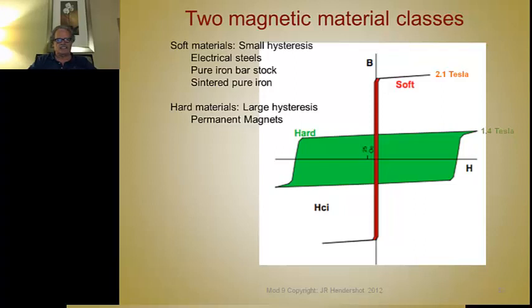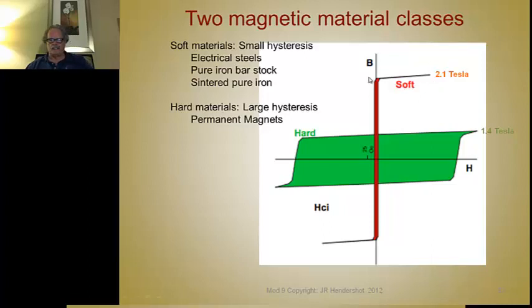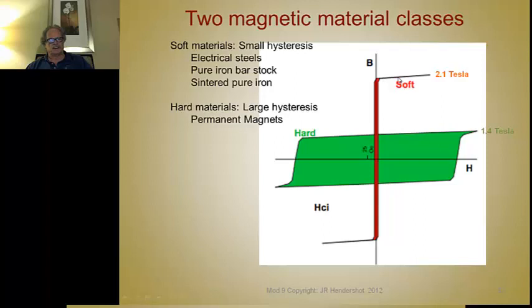The width of that red band is very narrow and that's what we want. Pay particular notice of the shape of the curve: it's almost saturated right at this point here. It's considered completely saturated out here, but there's not a whole lot of difference in flux density between these two points, and you pay a significant price in ampere-turns or magnetizing force to get the flux density from here to here.